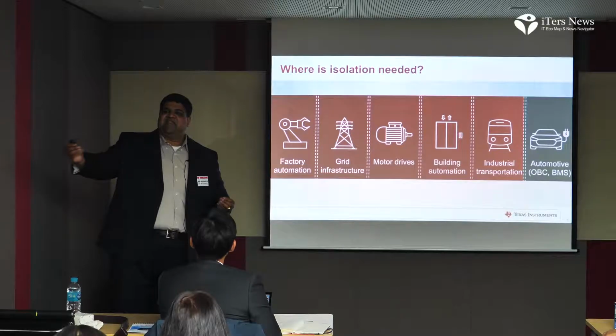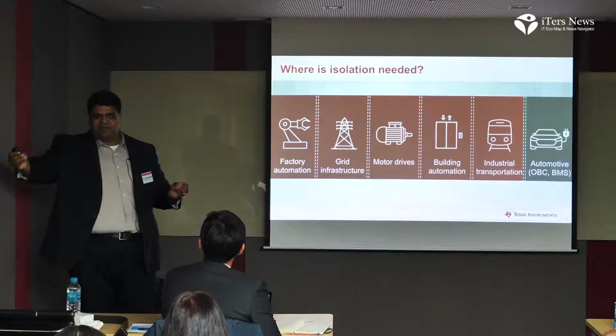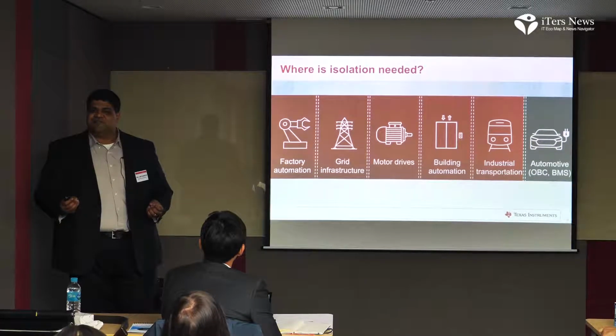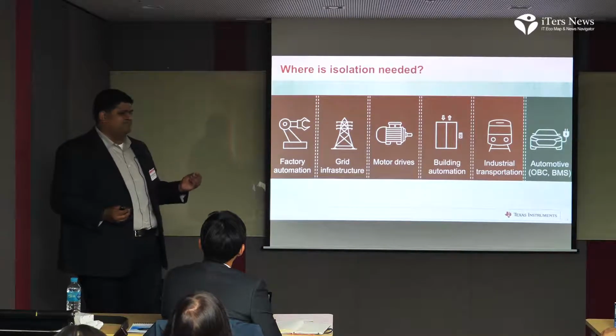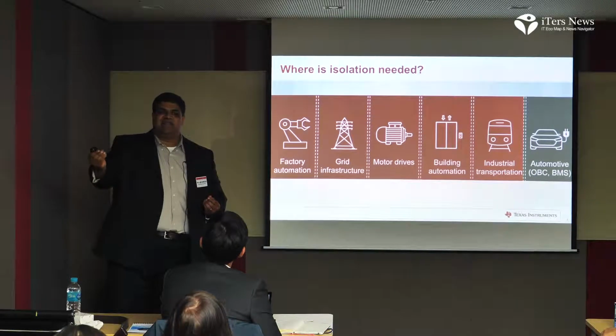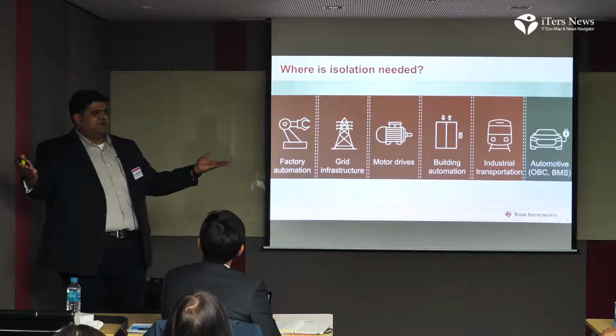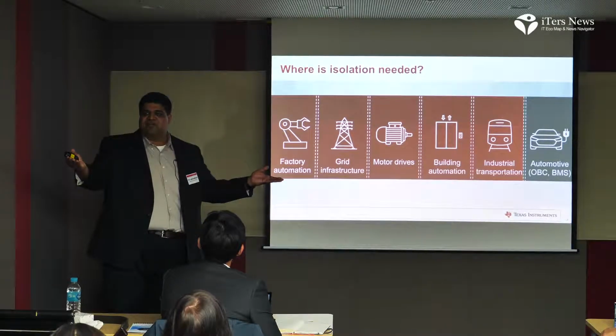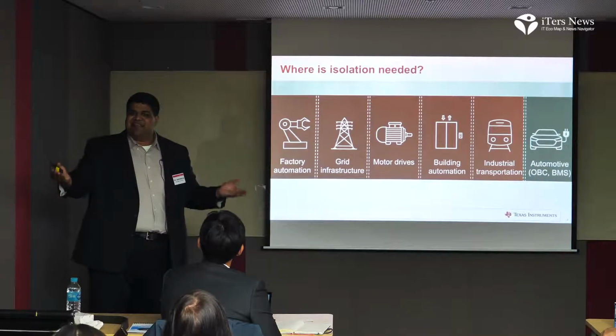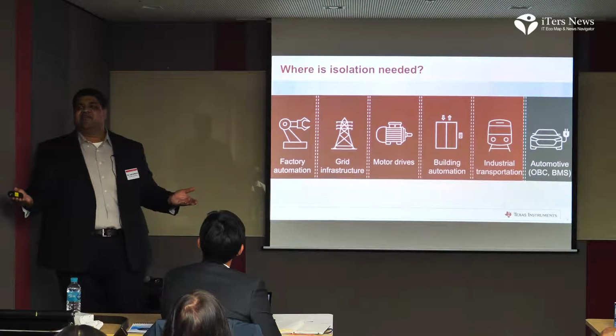And on the other side of that link, you may actually be sitting 100 meters away from the control room with maybe a 1,000 horsepower motor that you need to control. So when the command comes from the PLC for an actuator or something high energy to turn on, all of a sudden, the two grounds in between these two different control elements could be separated by about 50 meters to 100 meters. And at that point, the ground differential just by itself needs to be taken care of.